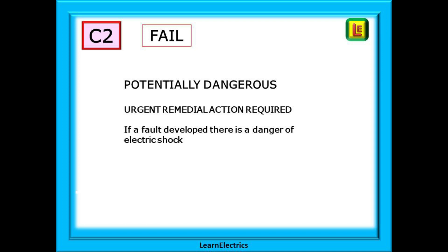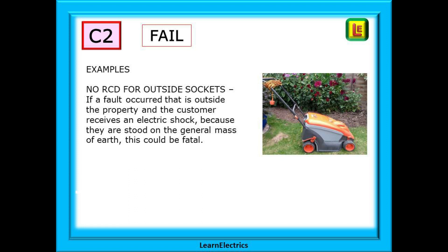Looking at the C2 type, this is also an automatic fail. It is classed as potentially dangerous and urgent remedial action is required. There might be no danger of electric shock right now at this moment, but if a fault developed there is then a danger of electric shock. An example would be a situation where there is no RCD for outside sockets and the customer has plugged in their electric lawn mower. The customer is not actually in danger whilst things are normal, but should the user cut through the cable, the ends may remain live, especially if plugged into a 32-amp circuit breaker. This actually happened a few years ago — the gentleman concerned bent down to pick up the cut cable and received a fatal electric shock.